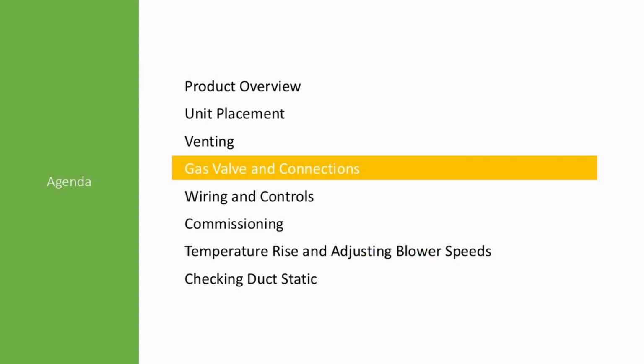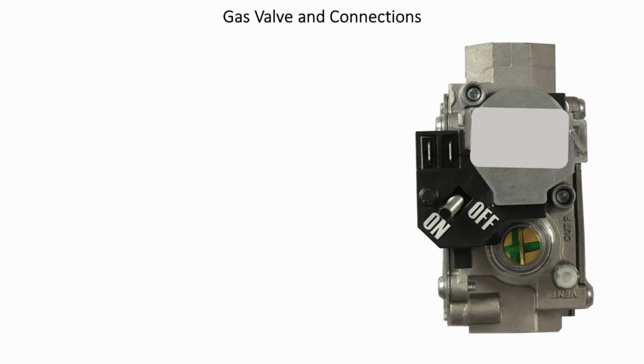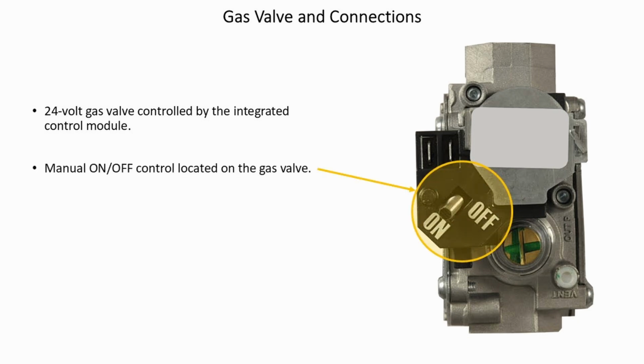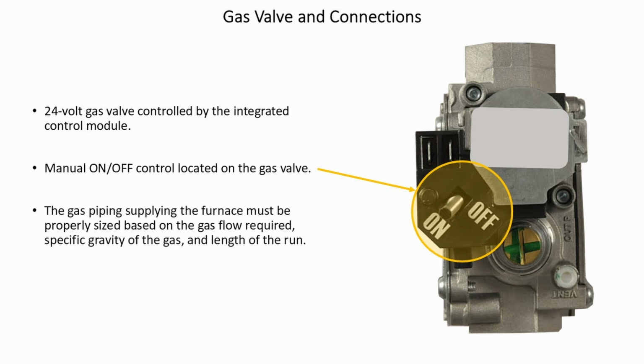Gas valve and connections. These furnaces have a 24-volt gas valve controlled by the integrated control module. They have a manual on and off control located on the gas valve. The gas piping supplying gas to the furnace must be properly sized based on the gas flow required, specific gravity of the gas, and the length of the run.